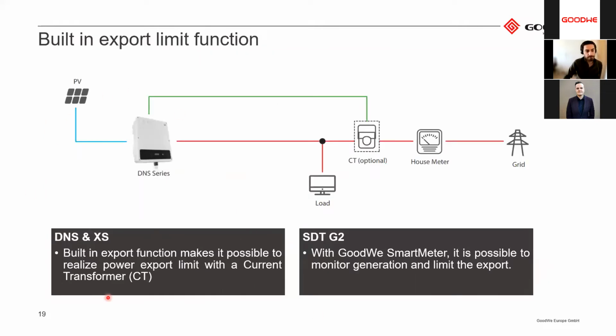Something that's very nice for our DNS and XS inverters is that they have a built-in export limit function. That means you can buy additional CTs and connect the CTs directly to the inverter. For our SDT G2 inverter, it works in a similar way. It also has this export limit function built in, but instead you need to have a smart meter in between. And then from the smart meter, you connect it to the inverter, and then also CTs to the smart meter. But it works in a similar way.